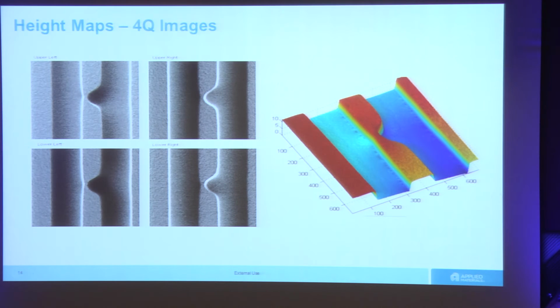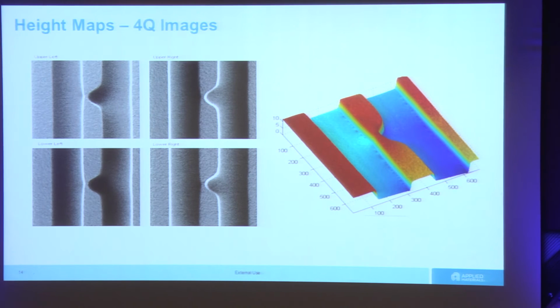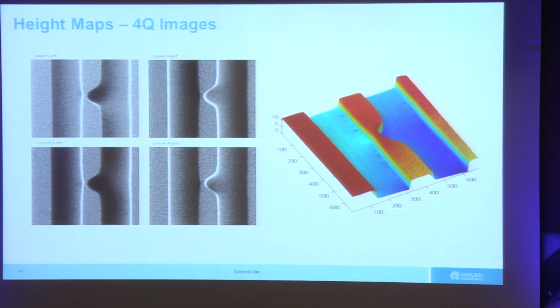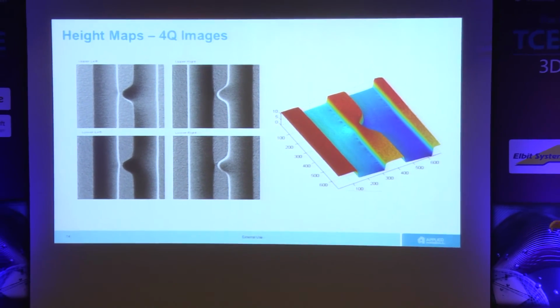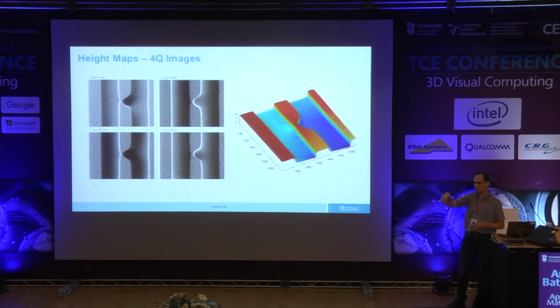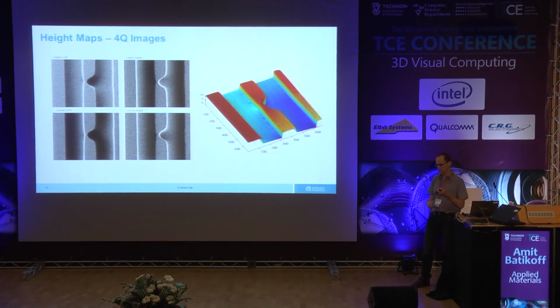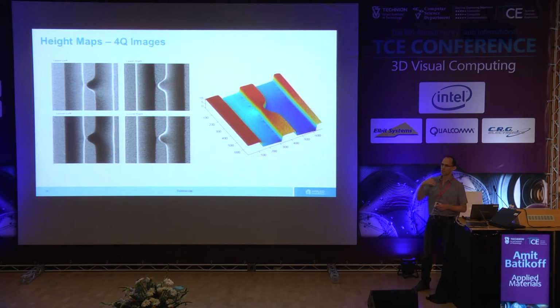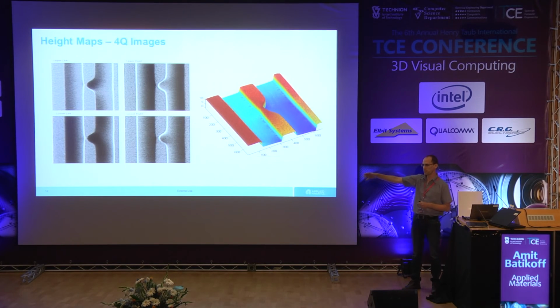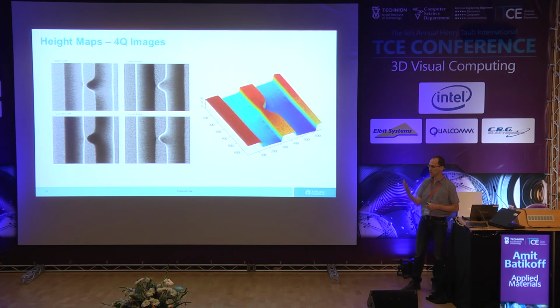So first of all, you can look at the images. You can see the light and shadow, and each of those detectors has this real direction, like 45 degrees from the sample. What's interesting to note is that it's different from the usual physical world, where the light source is what casts the shadow. Here, the light always comes from above, and the collection detector is what's being shadowed. So if we have a shadow on the edge of the left, it's because electrons that come out of the sample do not reach the relevant detector.